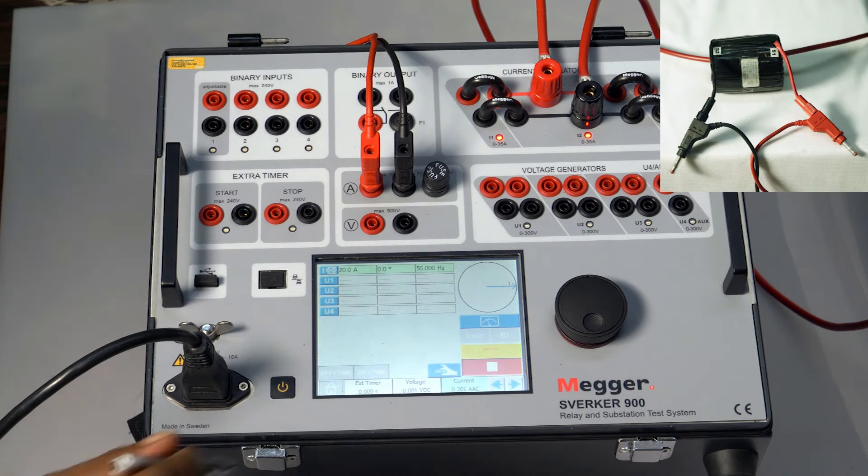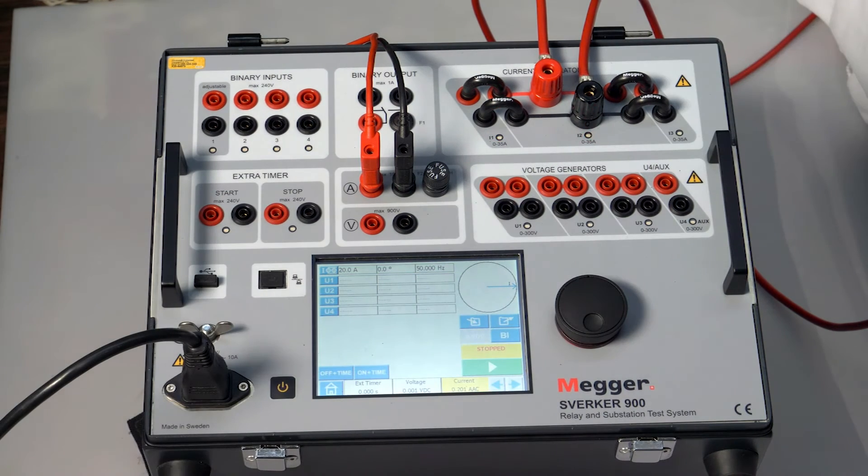And I will stop to note down the reading. The current is 0.201. Injected is 20 amps, 100:1 amps CT. Theoretically, the calculated value is 0.2. The measured value is 0.201.